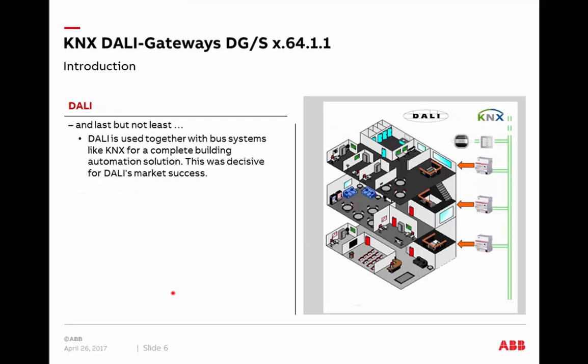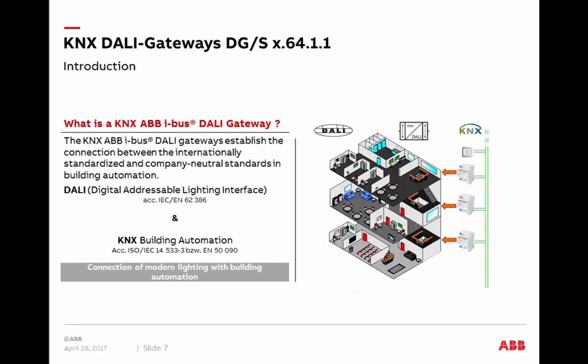A standalone DALI system still exists, but the success of DALI was largely generated by its integration into superior building automation systems like KNX. That is where we come in with our KNX and DALI gateways. For example, we may have one DALI-KNX gateway per floor in a commercial project, combining DALI with KNX in one complete system. DALI is an international, manufacturer-independent system standardized in IEC or EN norms, just like KNX. To bring both together, you need a gateway — that is our part.